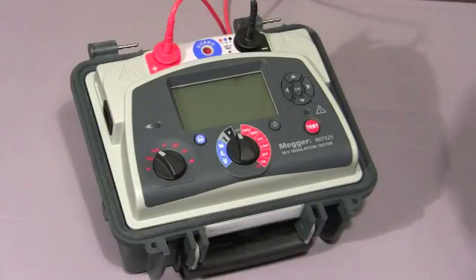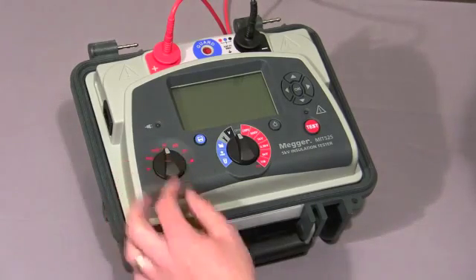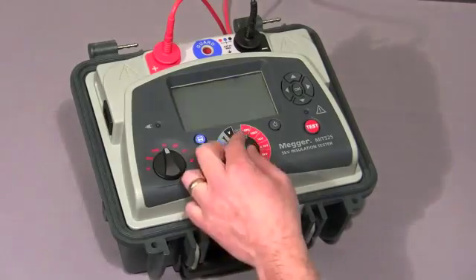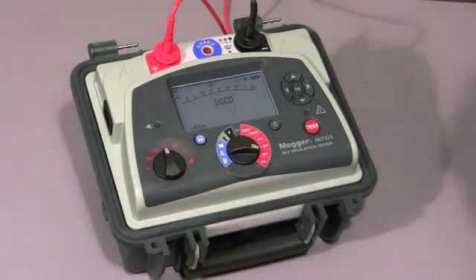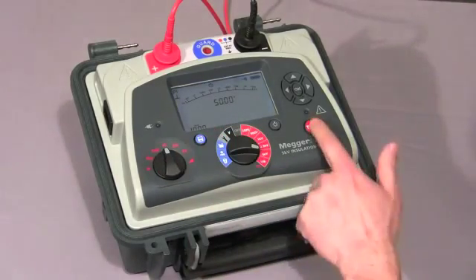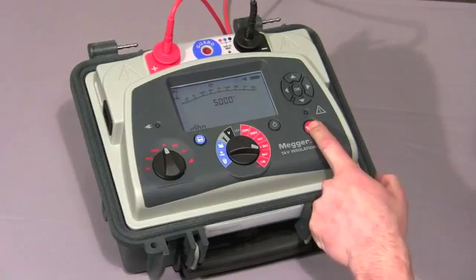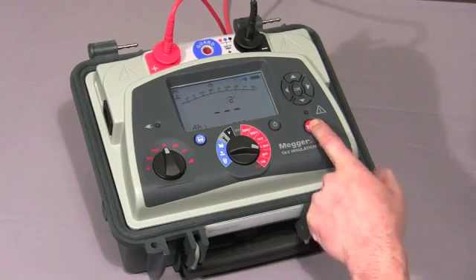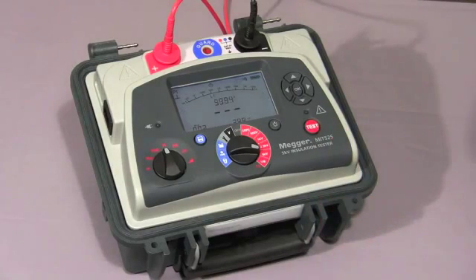I'll now show you a polarization index test. Firstly, we set the mode switch to PI, the range switch to the required test voltage, then press and hold down the test button until the test commences. The instrument will take a reading at 1 minute and at 10 minutes and then show you the ratio.